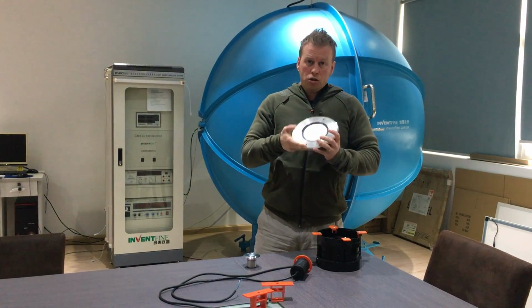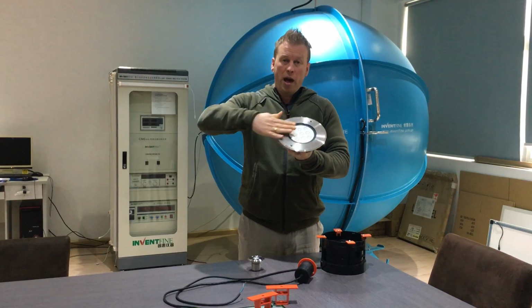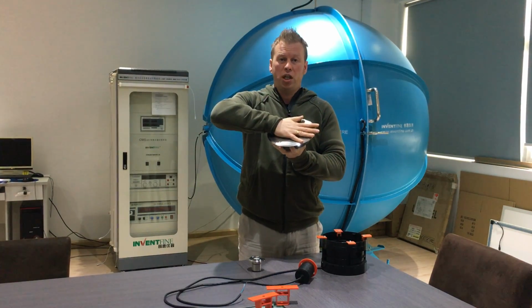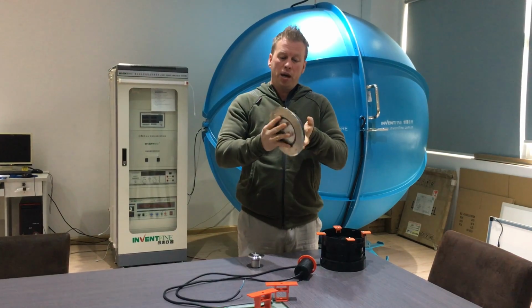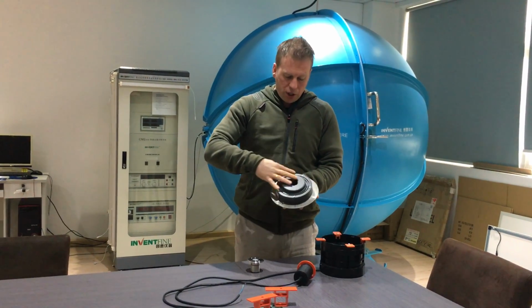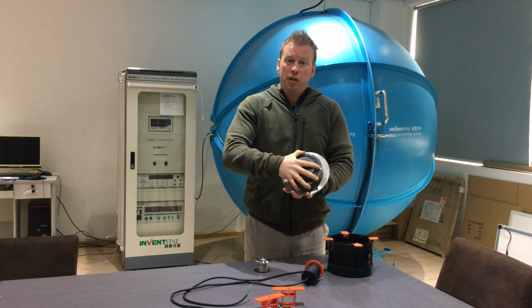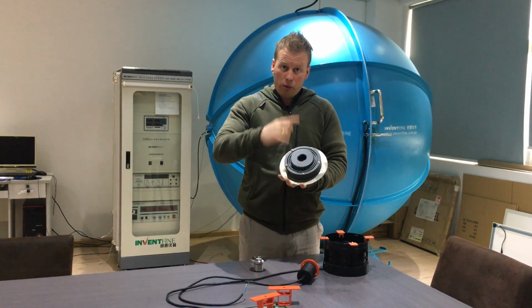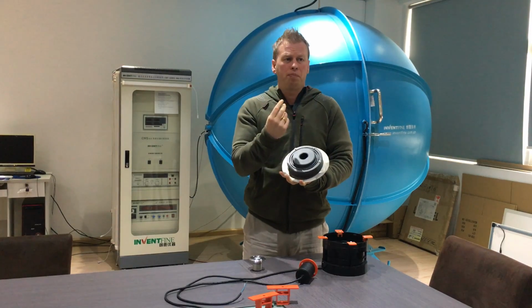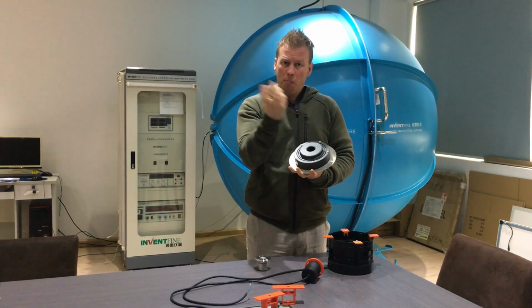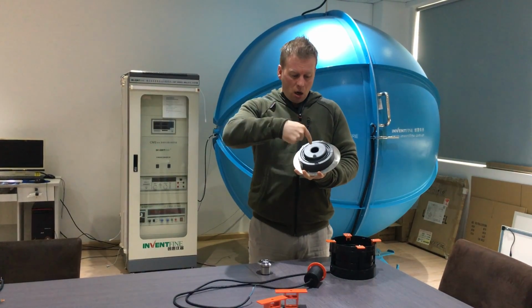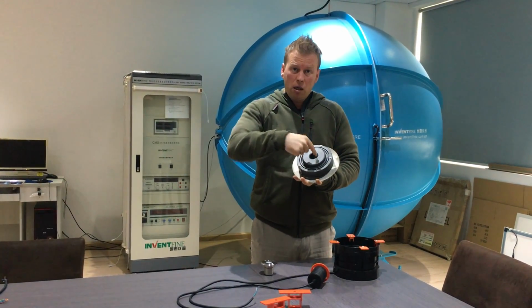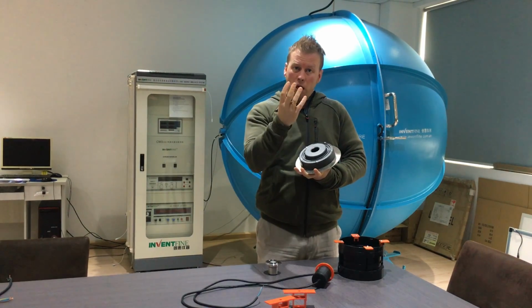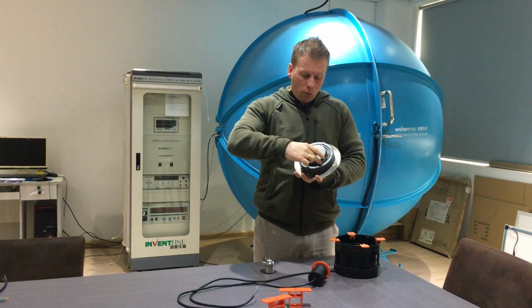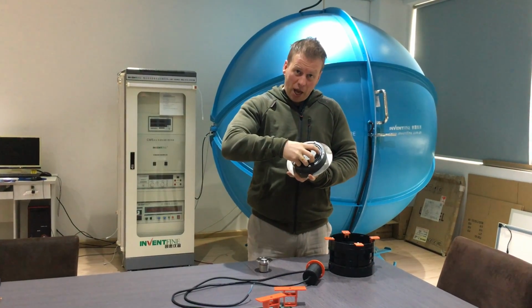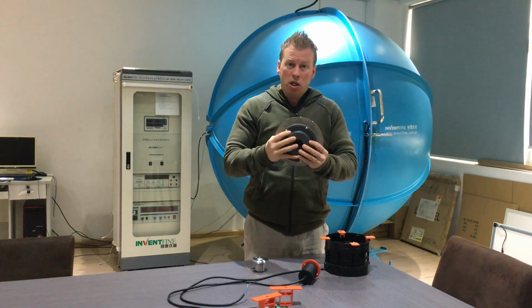The Illustro series works in two parts. You have the head here that is high pressure sealed, clamp sealed. Inside this die cast area, you'll feel it's quite heavy. It's got a magnetic coil, like a coil you'll find in a transformer, that picks up some current. When there's a probe placed in here, the probe has an EMF, and that generates its own power inside the head, which means you can keep this totally sealed.